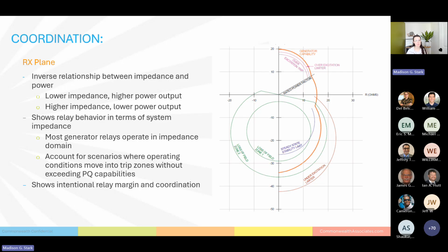So having the impedance coordination gives you a deeper insight into exactly how those relays are programmed and makes sure that you're not missing any corner cases or nuanced scenarios where you might be getting either trips that you don't want, or you might not be tripping in a situation where you need to trip. So this is kind of just a sister to that power graph. It gives you a lot of insight into exactly how those relay margins are developed and ensures coordination.